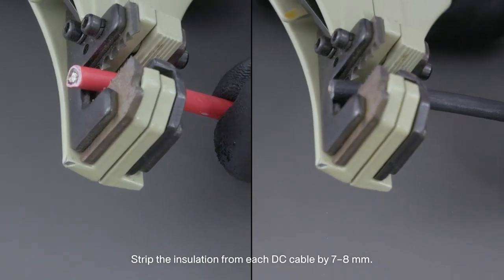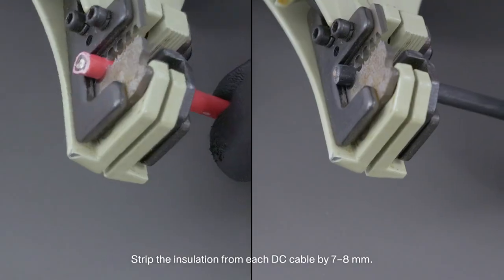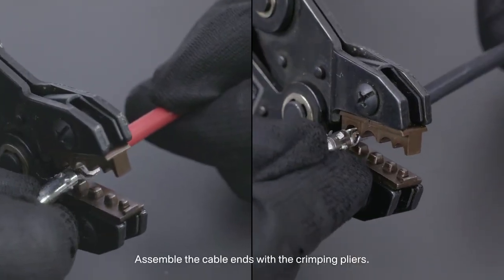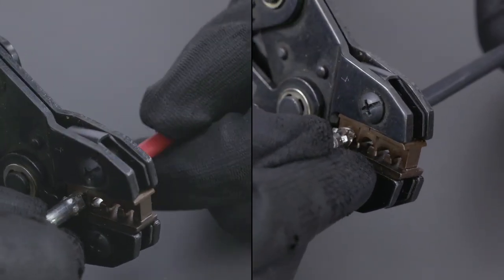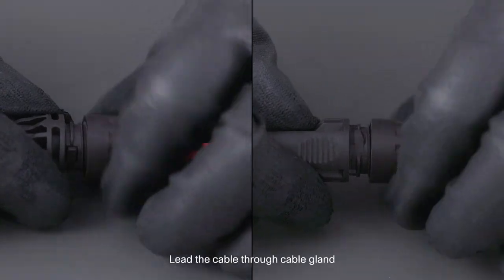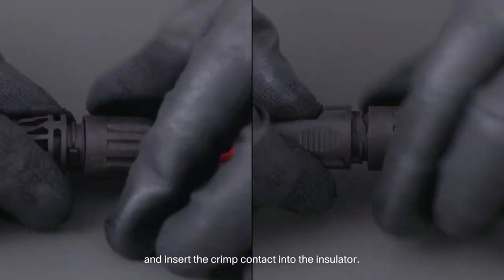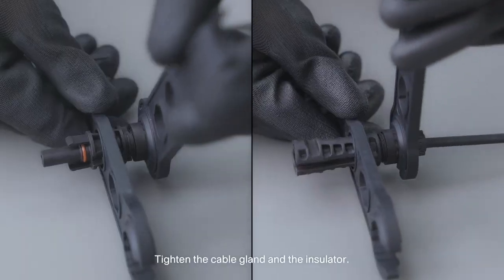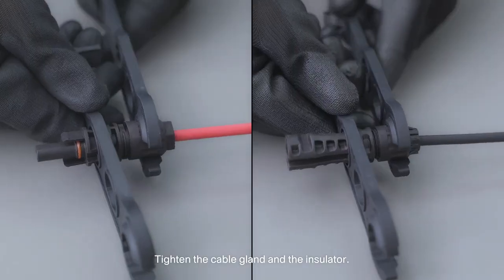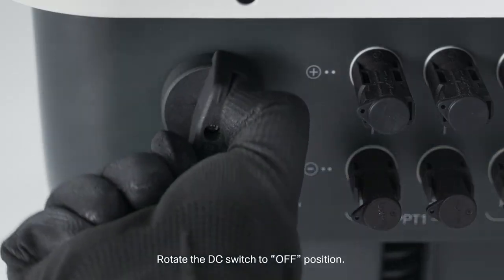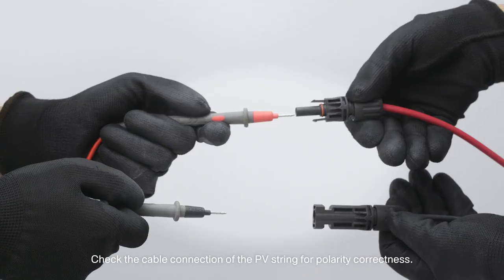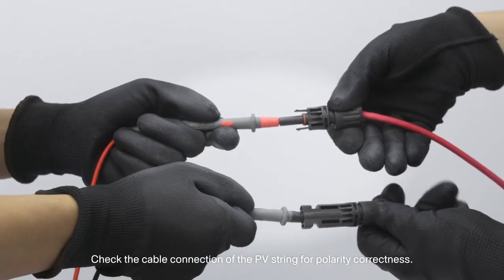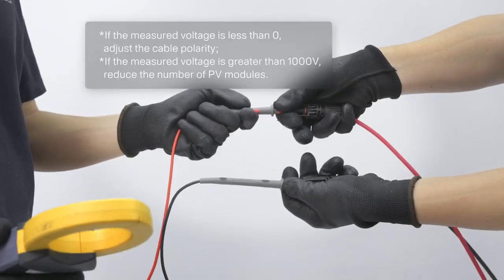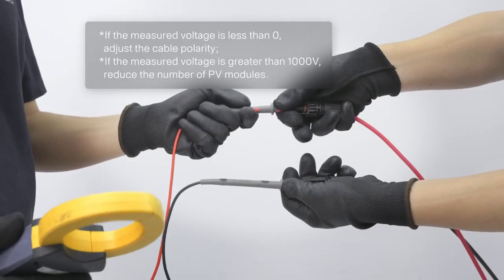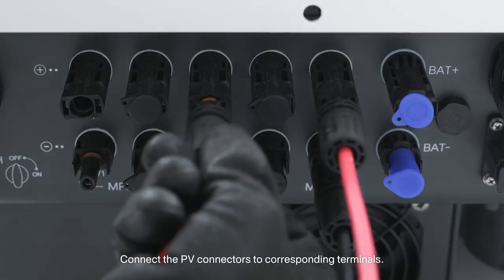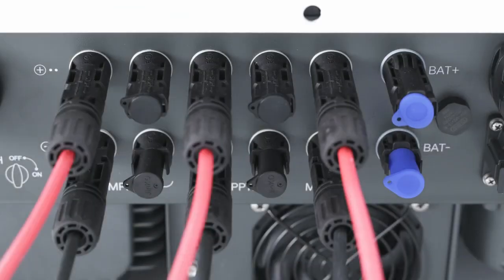Strip the insulation from each DC cable by 7 to 8 mm. Assemble the cable ends with the crimping pliers. Lead the cable through cable gland and insert the crimp contact into the insulator. Tighten the cable gland and the insulator. Rotate the DC switch to off position. Check the cable connection of the PV string for polarity correctness. Connect the PV connectors to corresponding terminals.